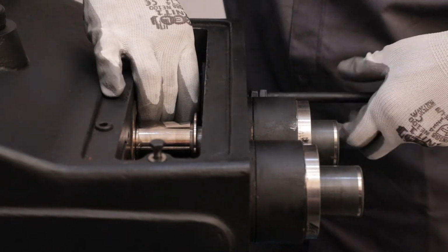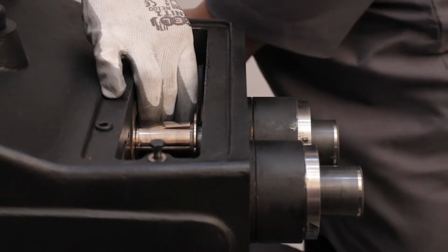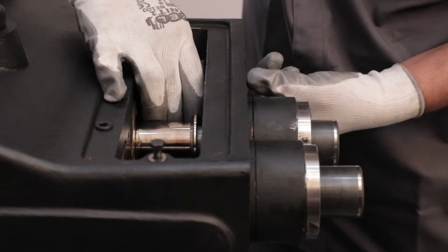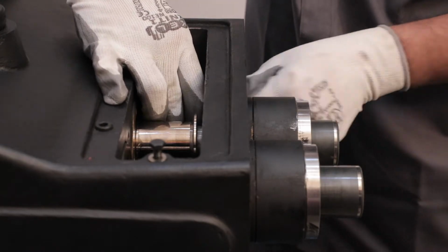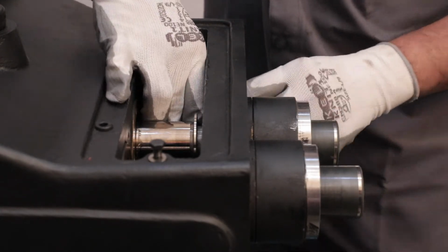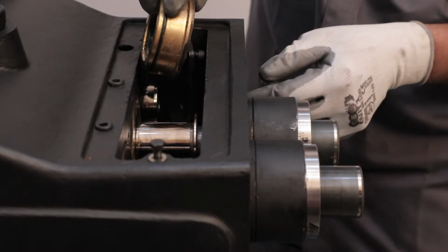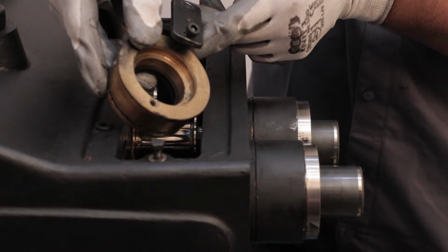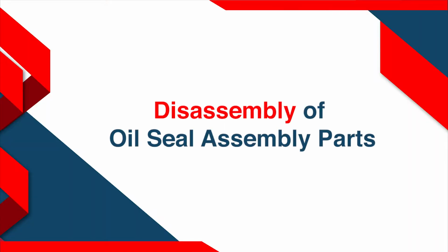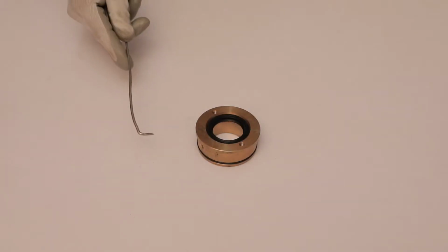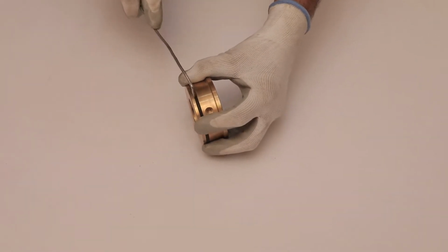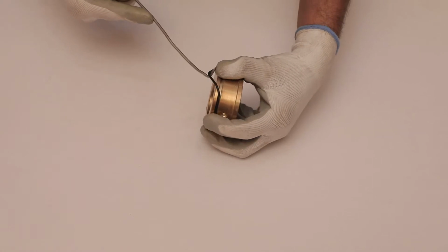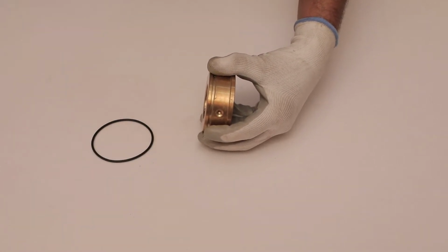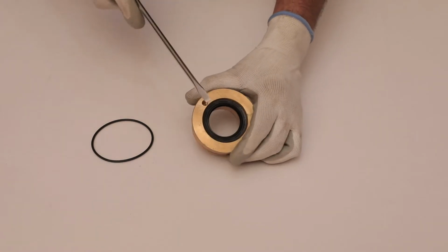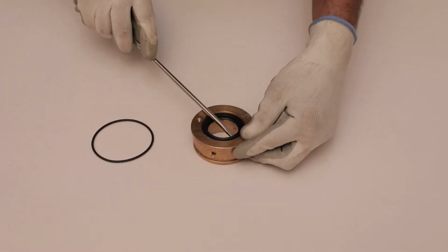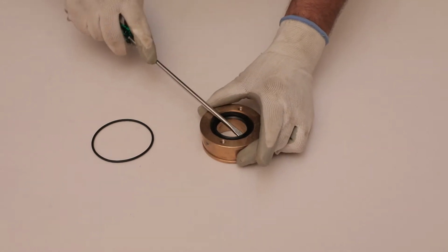Unscrew the valve puller from the strip and remove the strip from the oil seal cover to take out oil seal cover from crankcase. Place oil seal cover on a clear surface. Disassembly of oil seal assembly parts. With the help of pick, remove the O-ring on the periphery of the oil seal cover. Take a screwdriver and remove oil seal from the oil seal cover. Use a rubber hammer if needed.